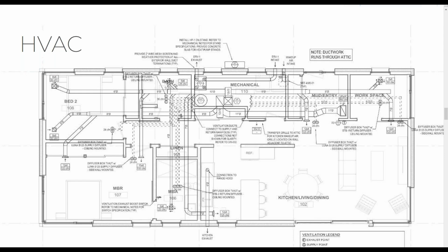You don't need to design more or build in more and overpower the system. So when you start getting the line between demands and design closer together, we need to make sure we're accurate. These duct plans have lengths of run on them, calculated for how many square feet and cubic feet of air are moving to each room, and how much air we're pulling out of each room. The balancing is already done for us as well, so I don't have one room that's overpowered versus another that's starving for heating or cooling.